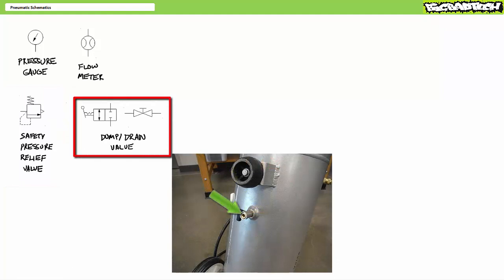Dump or drain valves are used to evacuate the receiver as part of a lockout and tagout procedure or regular maintenance activities. They might be schematically represented as a simple pair of opposing triangles or as two-by-two valves with a detented actuator, meaning that when you open it, it stays open, and when you close it, it stays closed.